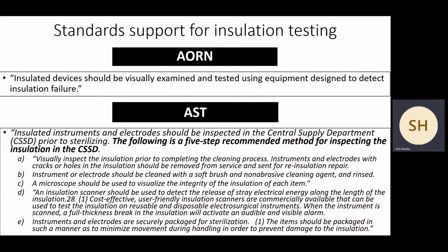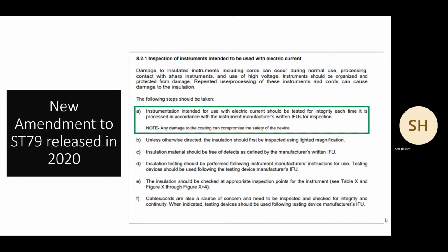So here we are again, preventing damage. And that's the 1-2 punch of this, right? Do all you can to not let them be damaged, but then inspect them each and every time, and in a way that you know, with a scanner, with a microscope, with both. Okay. Here's ST79, the release in 2020 about inspection. And we're just going to look at A here really quick. Instrumentation intended for use with electrical current should be tested for integrity each time it is processed in accordance with the instrument manufacturer's written IFU for inspection. Note, any damage to the coating can compromise the safety of the device.